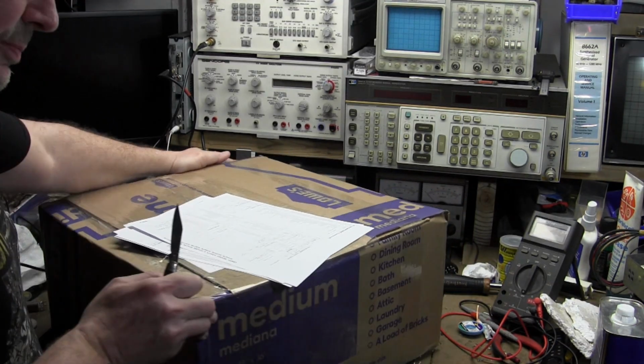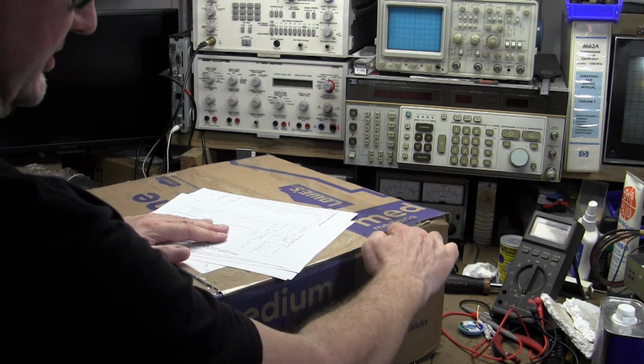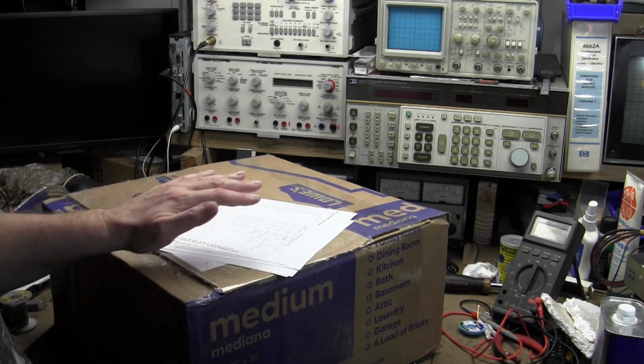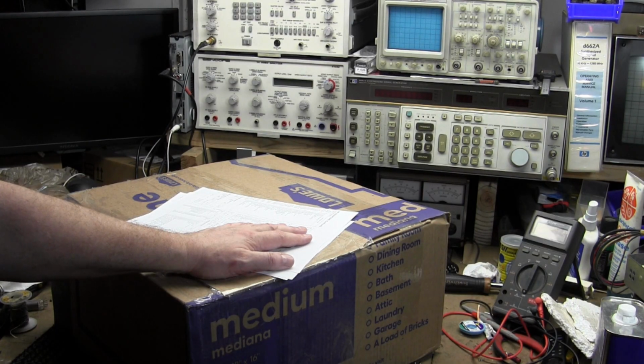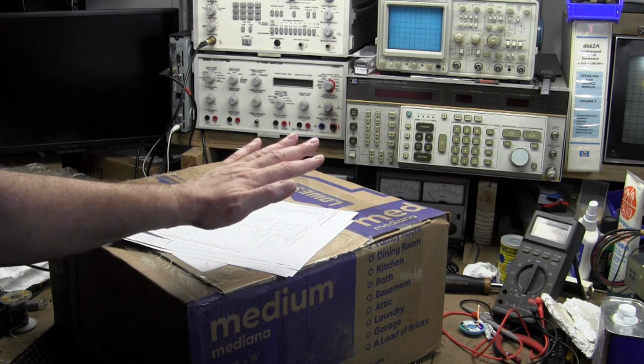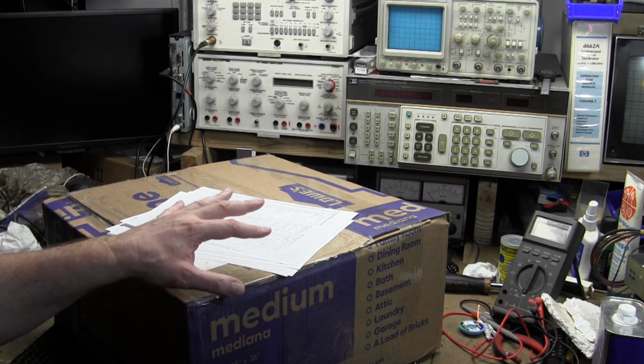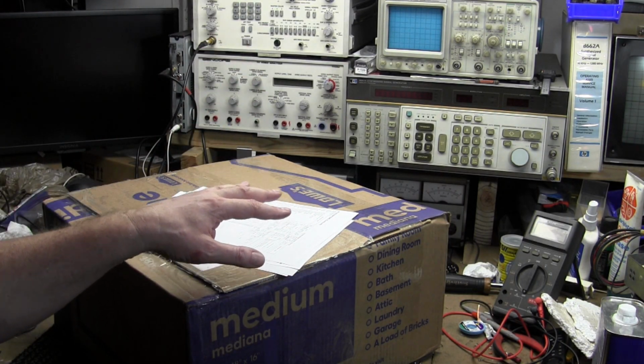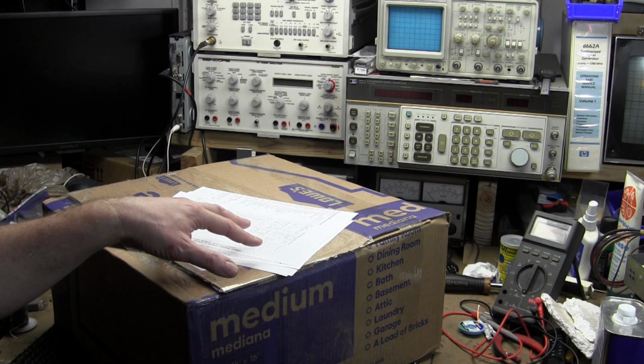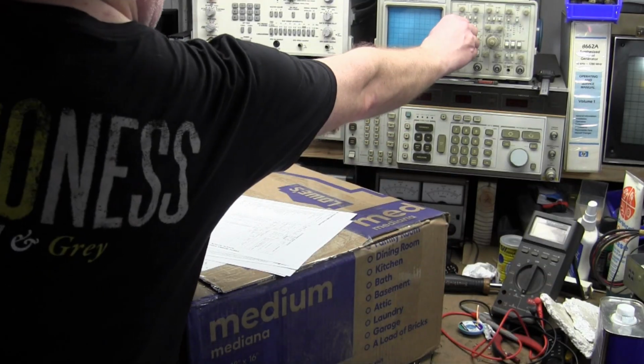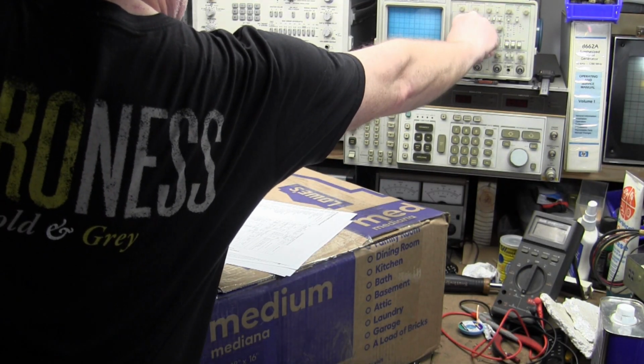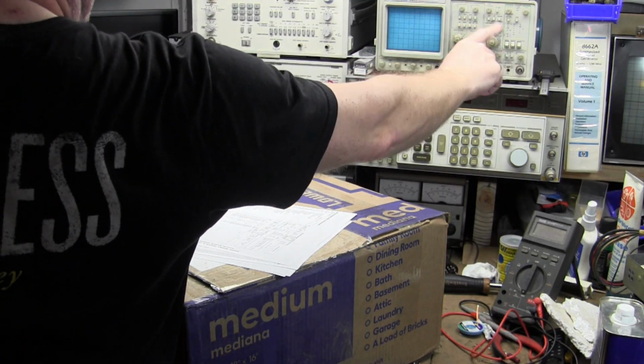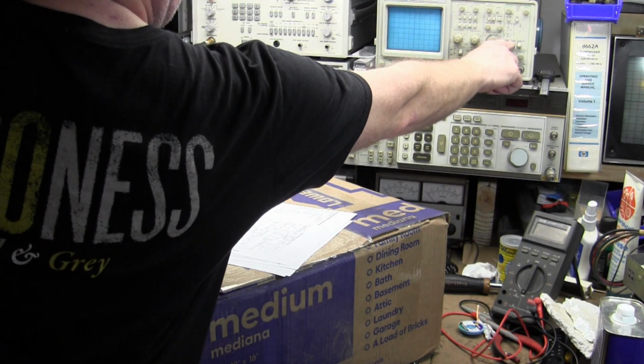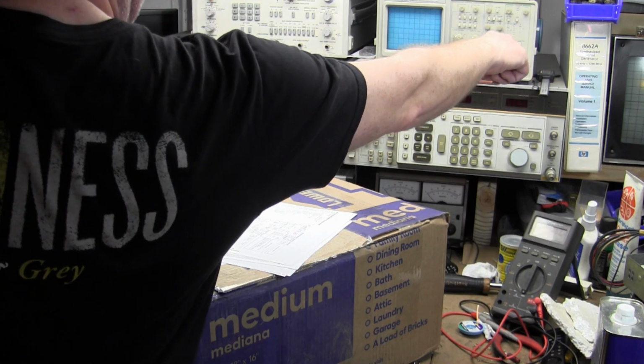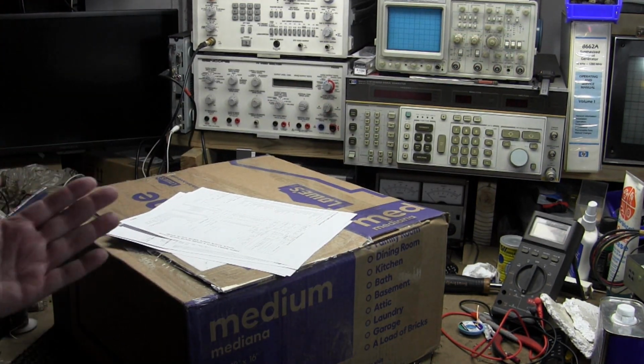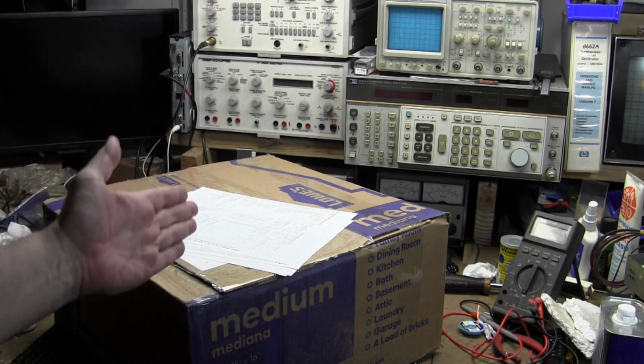They, or at least the B version for sure, uses one of those Dallas battery-backed-up static RAM hybrid chips. It's memory that holds both the calibration data and all the settings from when it was last used. Now, it's an analog scope, so the volts per division is a rotary knob, so what settings are there to save? Well, not everything, but some things like the source and coupling are paddle switches with numerous modes, and that's the kind of stuff that gets saved, so when you turn it back on, it's right where you left off.